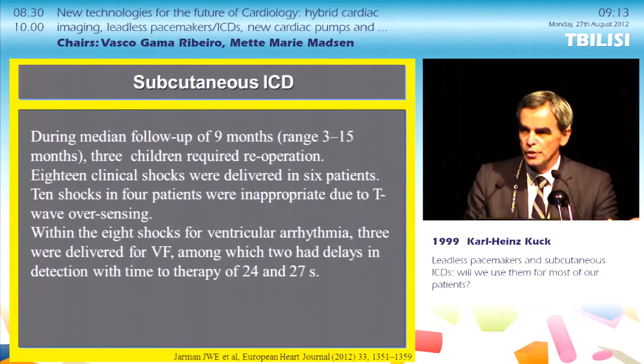So what is my recommendation before I would recommend that everybody should undergo such a device implantation? Of course, we know there are limitations. I would like to see that the DFT drops. I would like to see, and this is what we were asking for, the guys of the early days of the ICD, the sensitivity has to be 100%. We can't miss a single event of ventricular fibrillation. And we should not allow noise to prevent the ICD at the end of the day from shocking the patient. So VT-VF sensing is extremely critical to me.